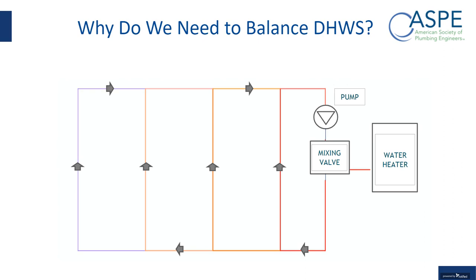But the idea is, once they're set up, this first riser, the one with the least resistance to flow and the lowest heat loss, is going to have the least amount of flow in it once the system is balanced. As you go from right to left, the adjustable flow in each of these risers will increase, so that the system becomes normalized, and the one all the way to the left will have the most flow, so that it will overcome the heat loss and the high resistance to flow. In theory, if the system is properly balanced, they will all have the same temperatures. That's the basic reason why we need to balance a system.